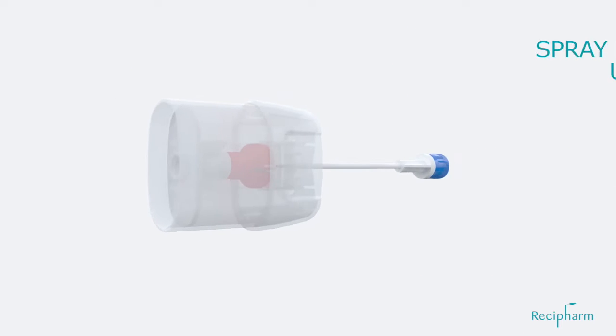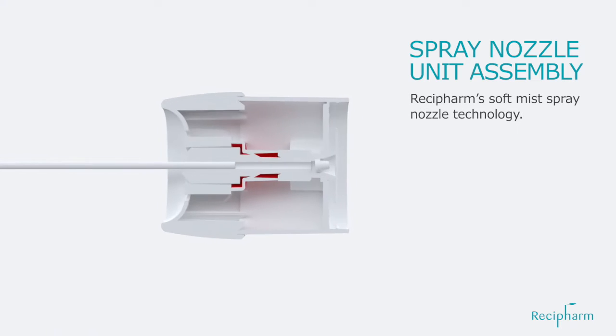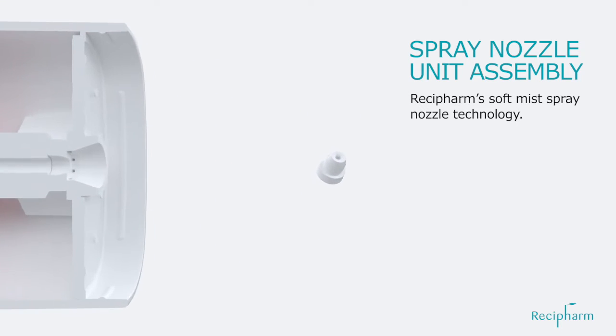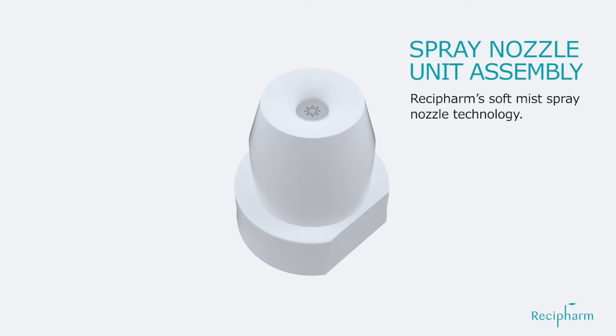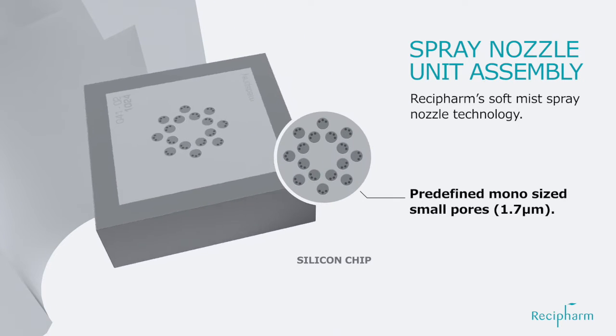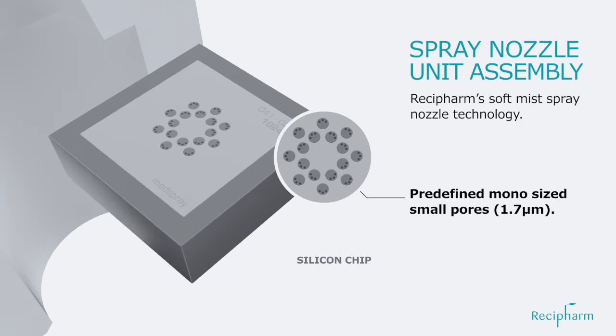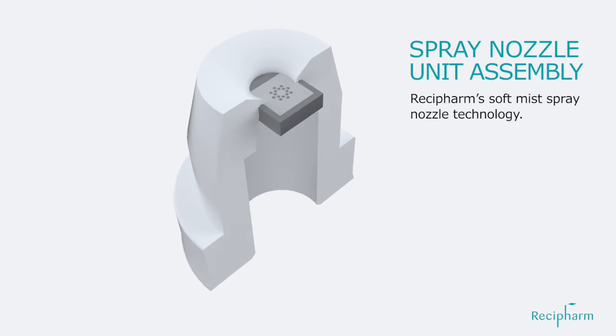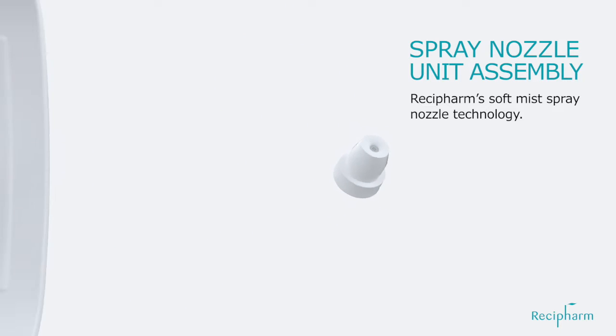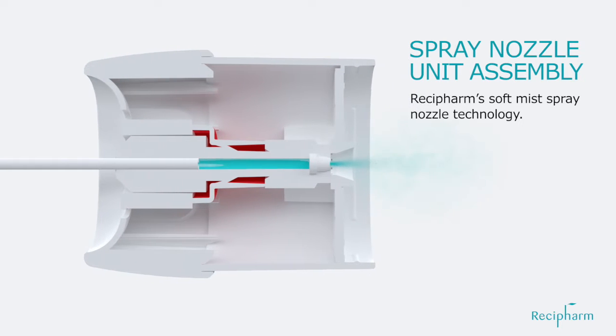To enable design of such a device, the Spray Nozzle Unit was developed — a simple yet effective technology for generation of soft mists. It consists of a silicon chip with predefined mono-sized small pores. Due to a differential in pressure, a liquid drug product is forced through the small pores, generating droplets due to Rayleigh breakup.